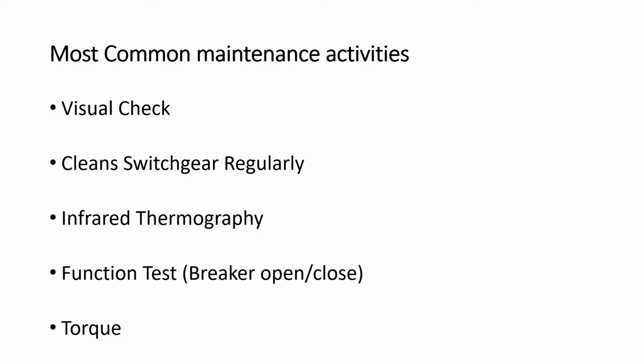So we had the utility shut the gear down. We operated the switch, and the three blades stayed stuck while the arm kept operating, and it broke all three blades. So what would have happened if we'd actually opened it with a load? We were all looking at each other. I looked at my technician and said, you open it. We looked at facilities and said, you open it. He said, I'm not opening it. So common sense prevailed.